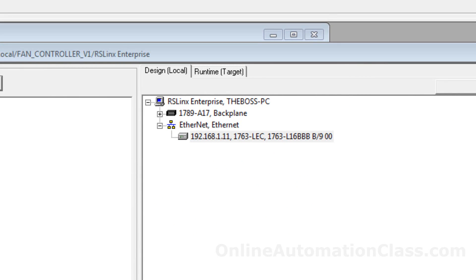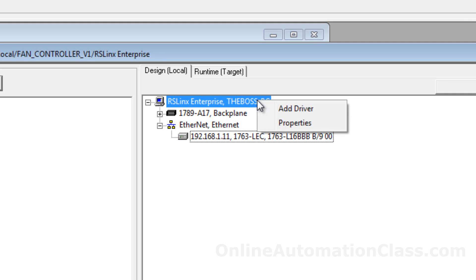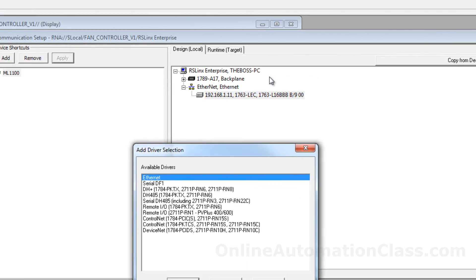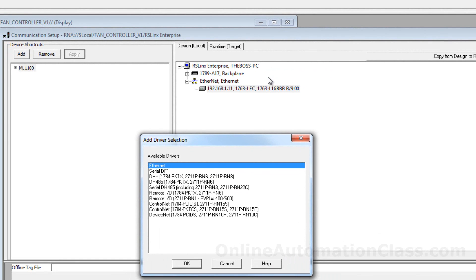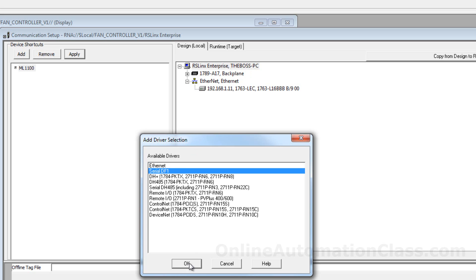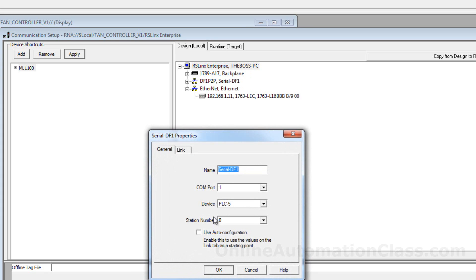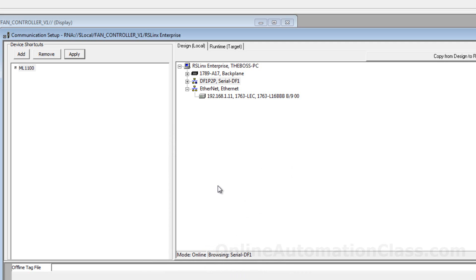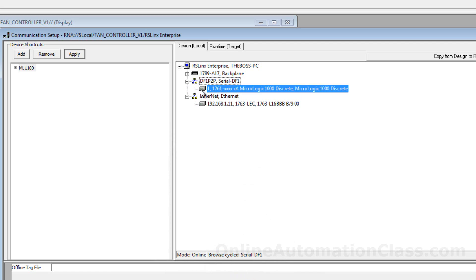If the desired communication driver is not seen, one can add it by right-clicking on RSLinx Enterprise and then select Add driver. To demonstrate, a serial DF1 driver is added and configured to detect a MicroLogix 1000 PLC. The COM port is set to 4 and use Auto configuration option is selected. The MicroLogix 1000 PLC can be seen when the serial DF1 driver is expanded.